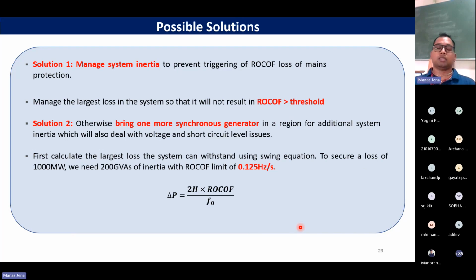Let us discuss a couple of possible solutions. Manage system inertia to prevent triggering of RoCoF-based loss of infeed. So essentially, manage the largest loss in the system. In our system, let us say, what is the worst case possibility, what is that megawatt which I can lose, and that should be my worst case. Is it 100 megawatt, is it 4000 megawatt? Prepare for that one. So manage the largest loss in the system so that it will not result in a RoCoF greater than the RoCoF threshold, whatever our operator is using.